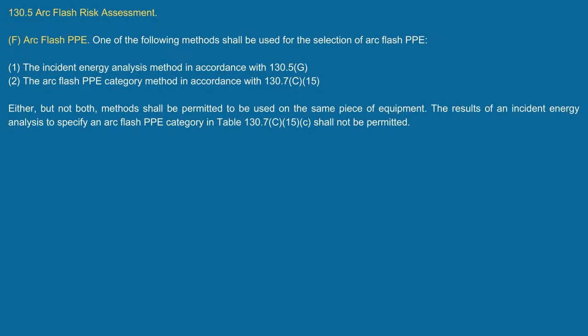And it says you can do the incident energy analysis method, which is what we just did for arc in open air and in a cubic box. And then it tells you that I can select the PPE based on what? 130.5 G. And if I'm using the arc flash PPE category method, I can use what? 130.7 C15. I'm going to show the difference in these.